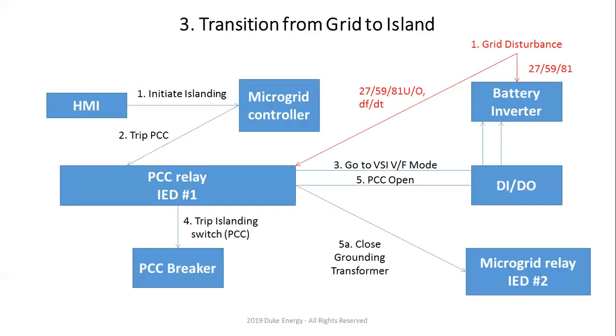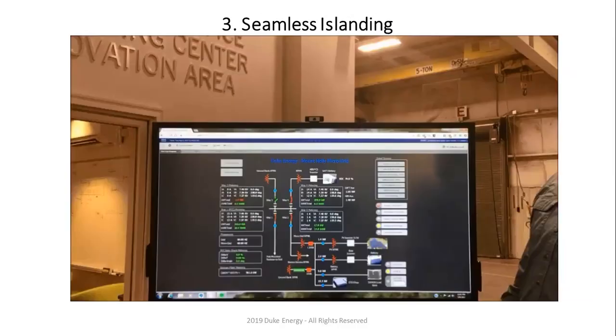If you have a grid disturbance, everything is the same except that either our battery inverter or the PCC relay senses 27, 59, and 81. Now, there's a whole lot more to it. I have a couple of extra pieces that we sense later on, but pretty much the same. So if the battery senses first, it will send the information over to the PCC relay to trip. It's going to go through the same procedure. If the PCC relay senses first, it's going to tell the battery the same way.